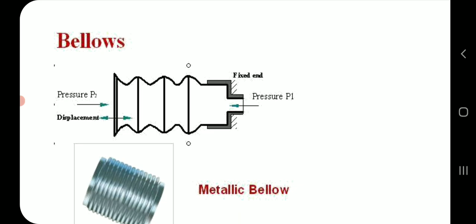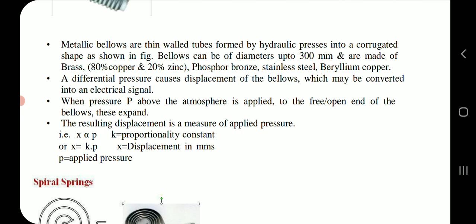Bellows. Pressure P1 and P2, displacement, fixed end, metallic bellows. Metallic bellows are thin walled tubes formed by hydraulic presses into a corrugated shape as shown in the figure. Bellows can be of diameters up to 300 mm and are made of brass, 80% copper and 20% zinc, phosphor bronze, stainless steel, beryllium copper.